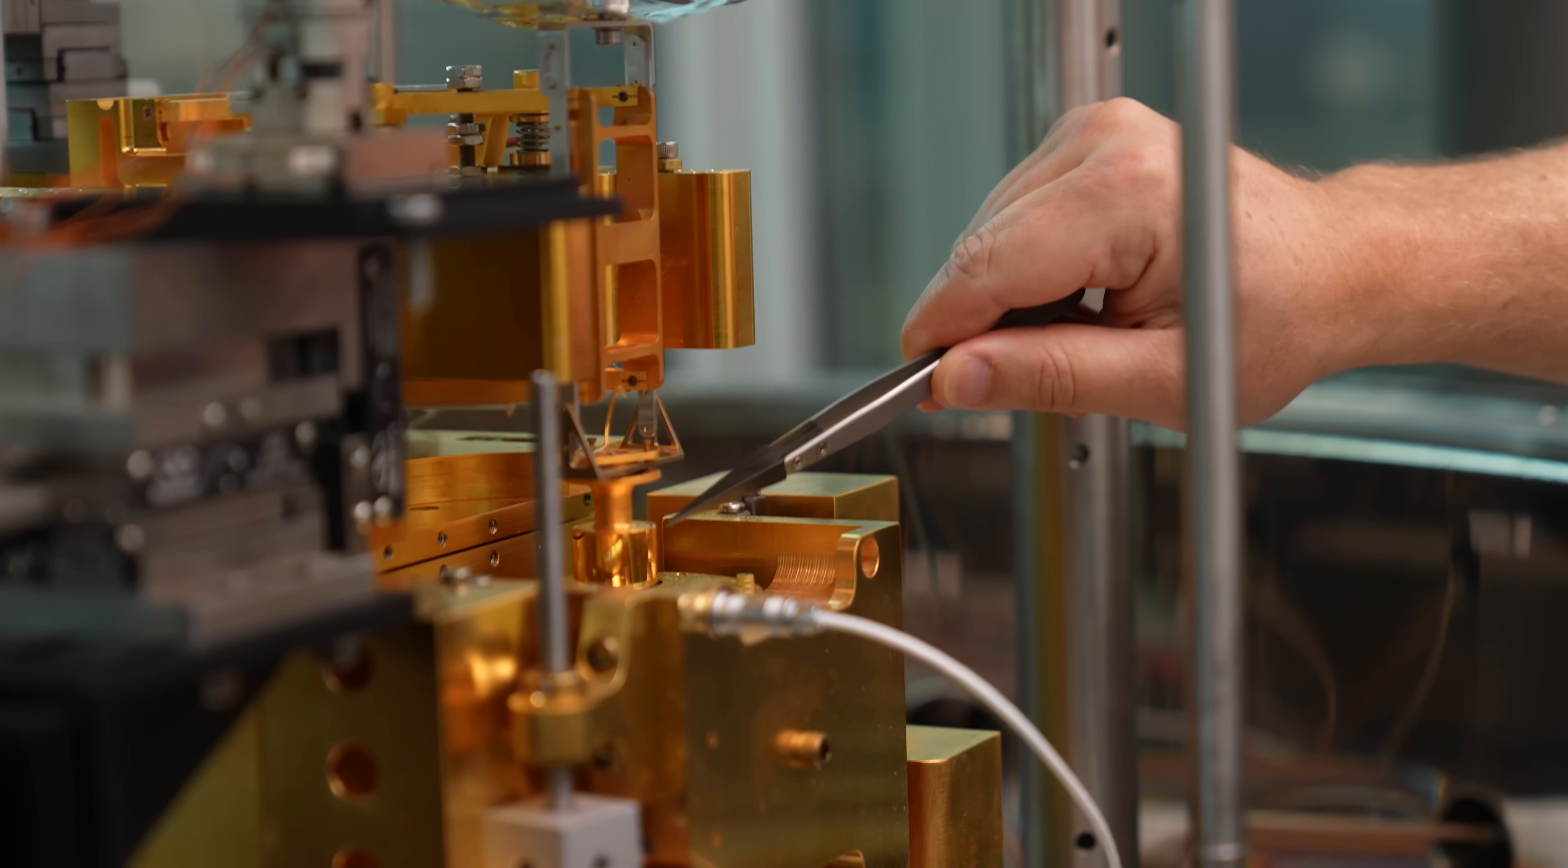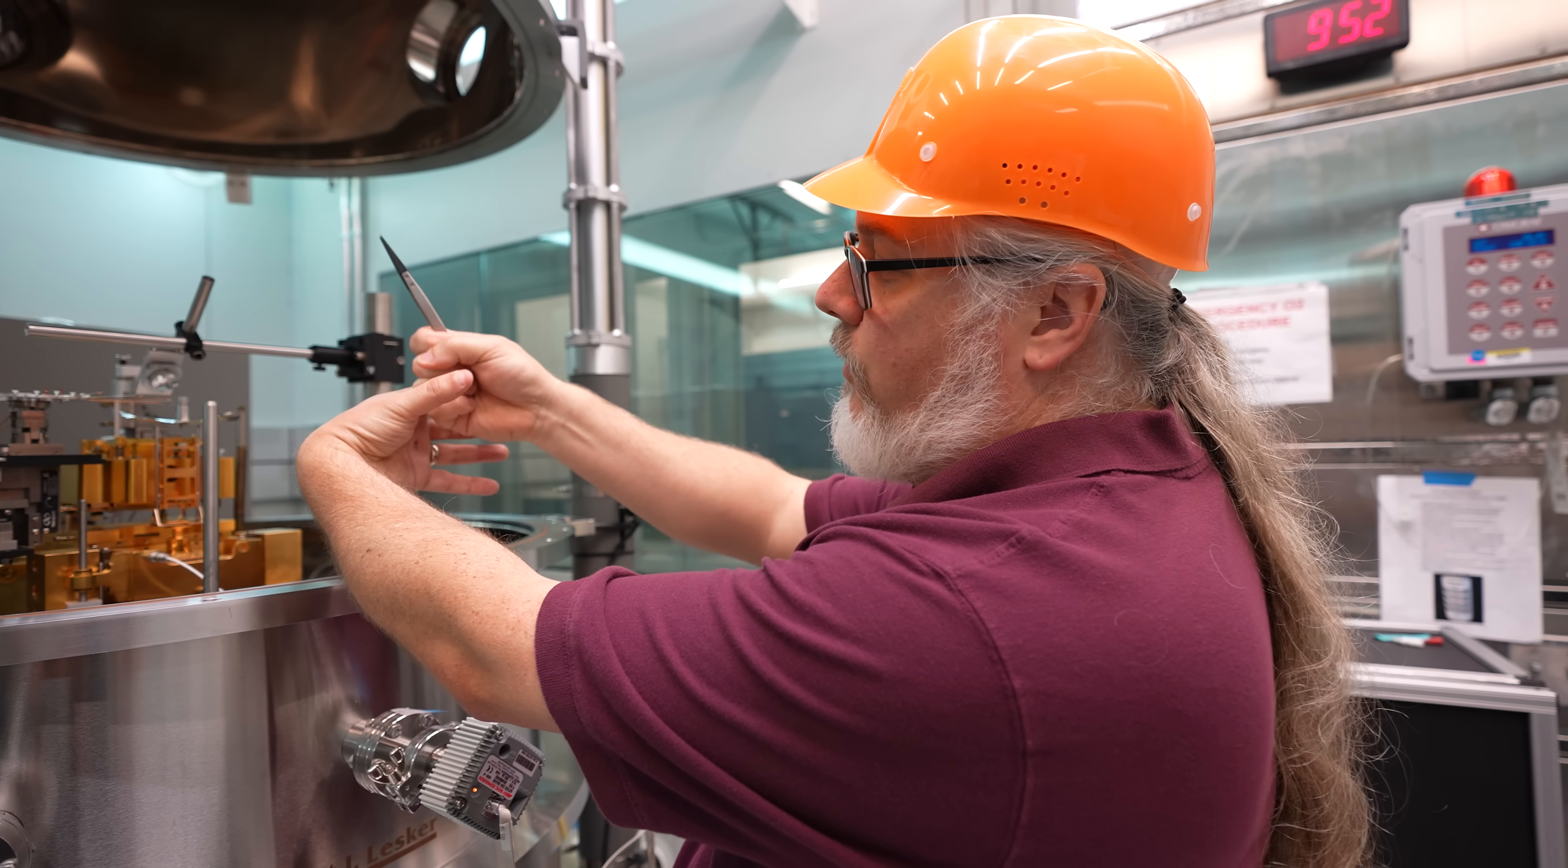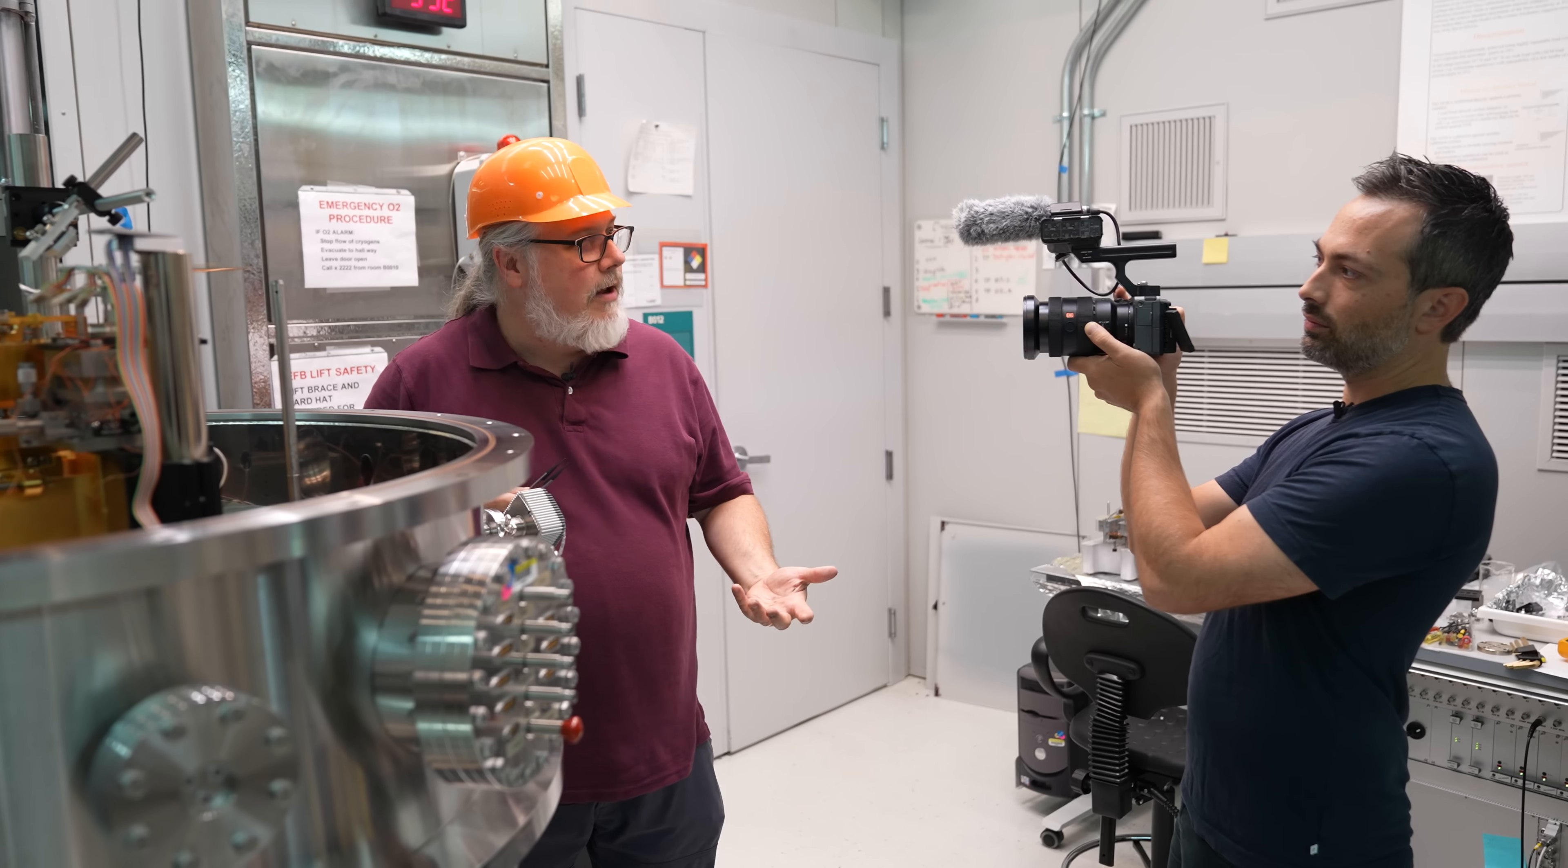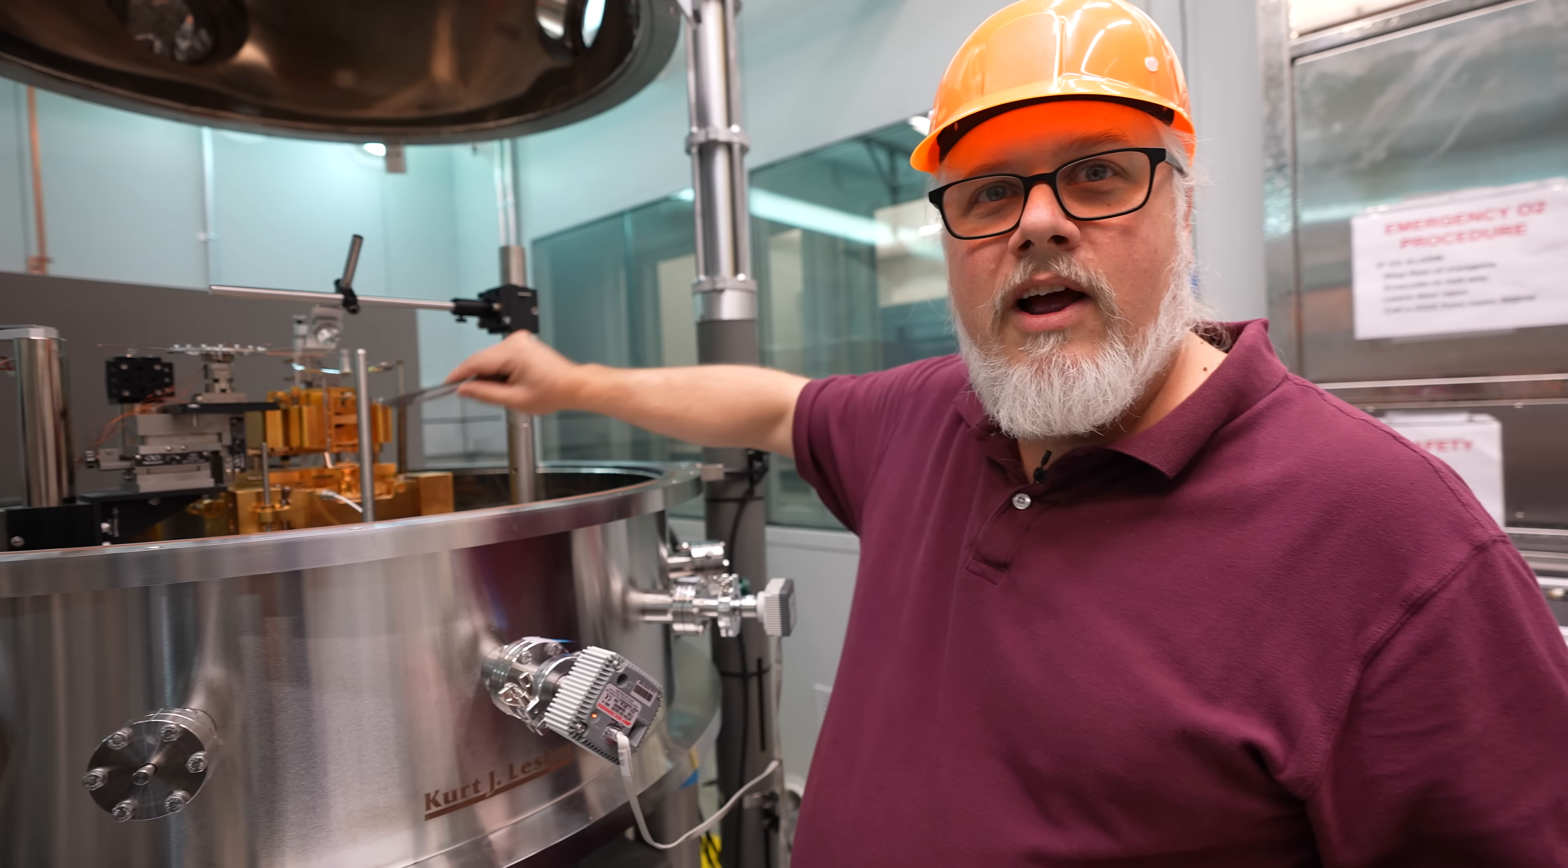I apply an electrostatic force by applying a voltage here at this. You can see this cylinder here. There's this cylinder and inside of this, there's another cylinder and they're close together. So you have this concentric cylinder like this. And when you apply a voltage, it pulls that moving cylinder down in there. And by measuring the properties of the capacitor and measuring the voltage that we apply, we can know exactly how much force we get here. And then up here, we drop our mass on. So we compare our gravitational force from the mass to the electrostatic force from our capacitor.